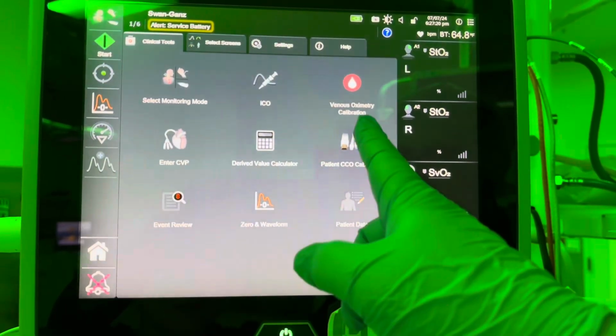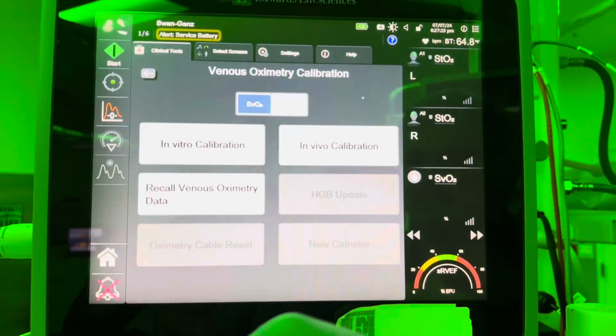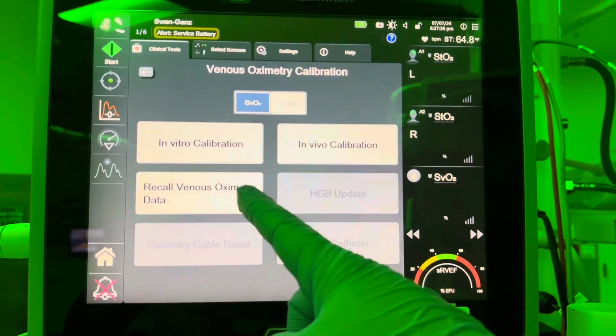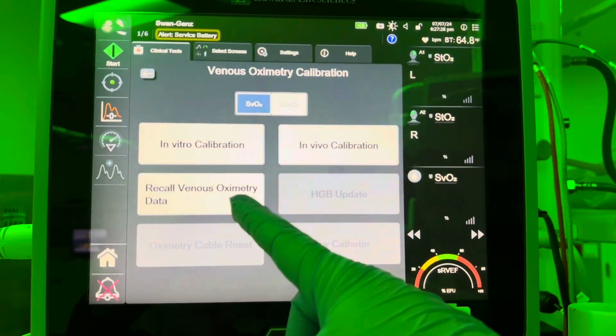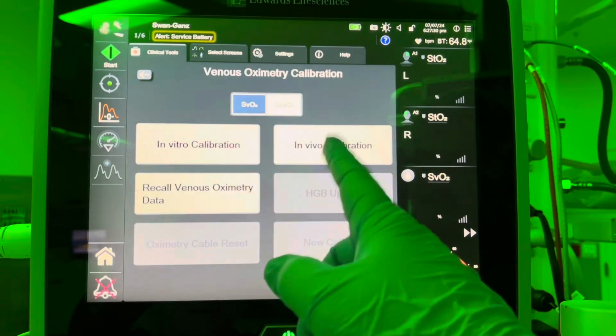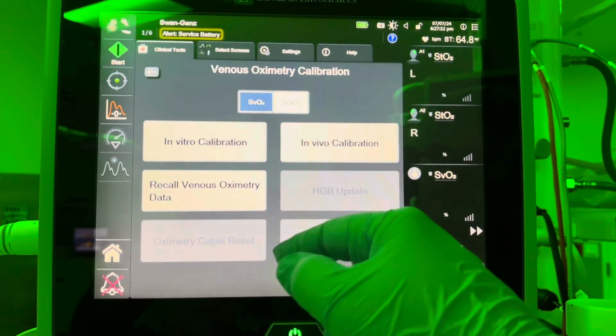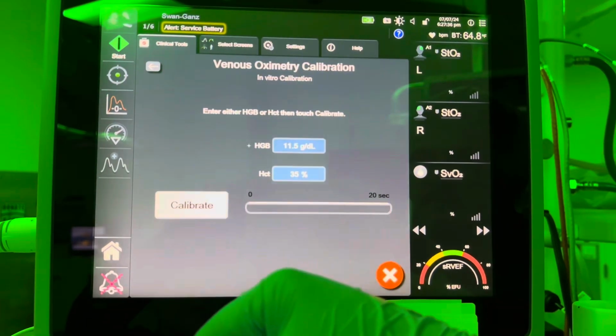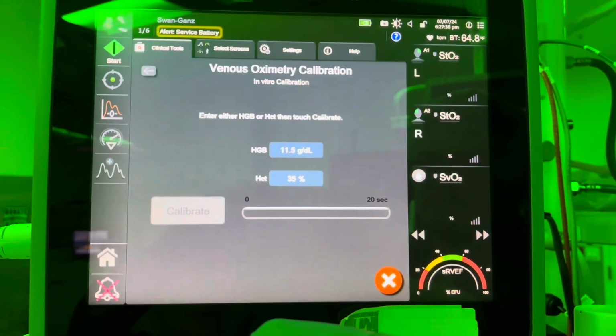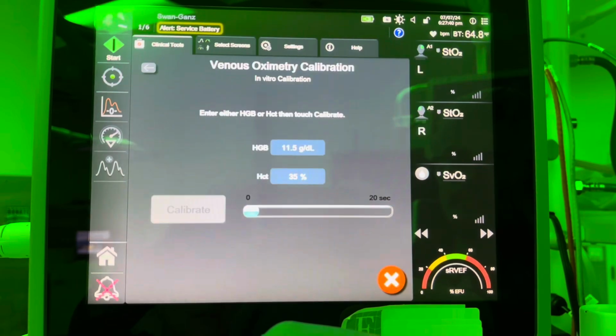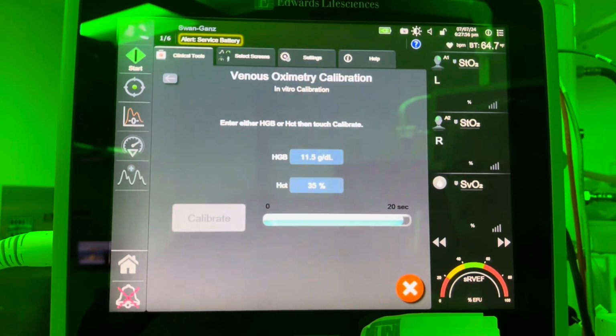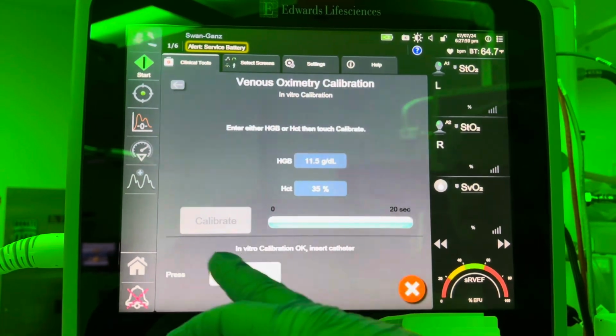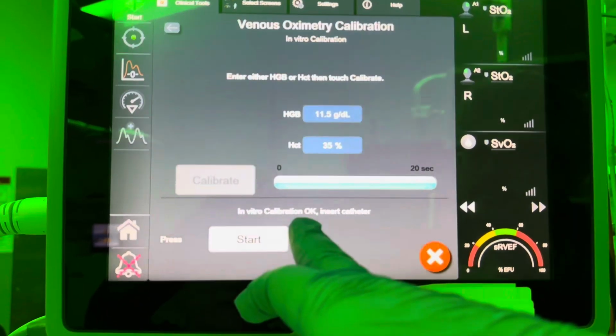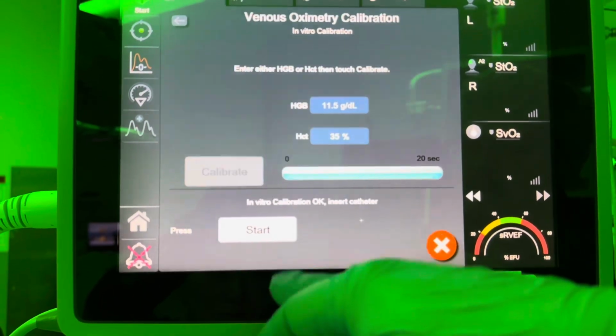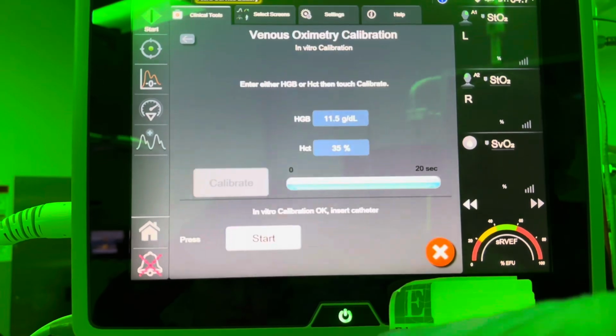And we go to venous oximetry calibration on the top right. So in vitro calibration means outside of the body when you're calibrating it, and in vivo means the catheter is inside the patient. So since we don't have a patient, we do in vitro, and you can press calibrate. And it'll give you this pop-up screen. The calibration is okay, and you can insert the catheter. And you'll press start when it's inserted.